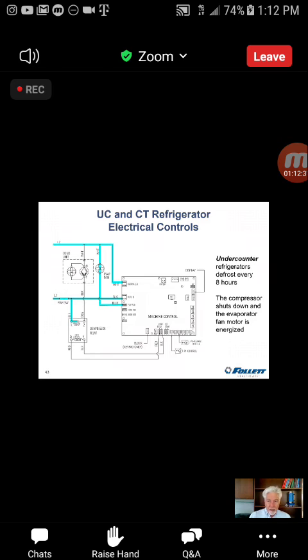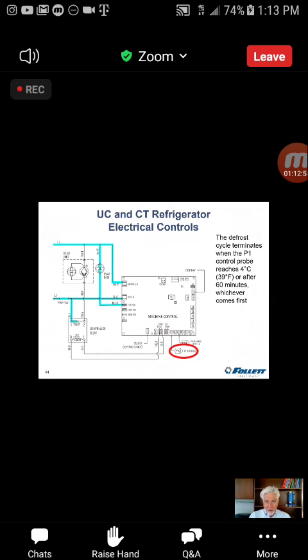So all that happens again in this defrost cycle is we shut down the compressor, we energize the evaporator fan. So we're just using the air that's above 32 degrees in the refrigerator and circulating it through that defrost termination probe, which is through the evaporator. And when the P1 probe gets to 39 degrees, okay, which is 4 degrees Celsius, that is when we terminate the defrost. Or after 60 minutes, that's the length. And like I said, typically, if we terminate on time, you're going to get a DFA alert. All right, it's just letting you know.